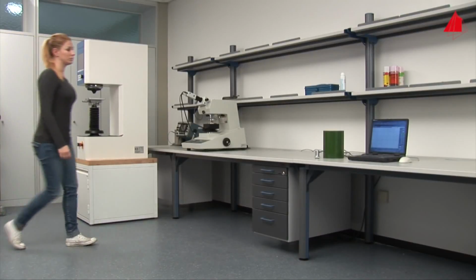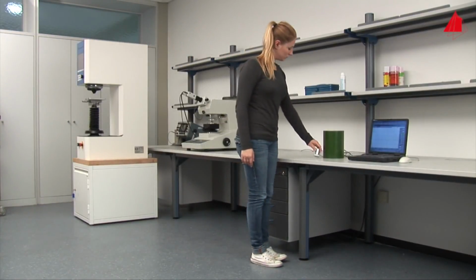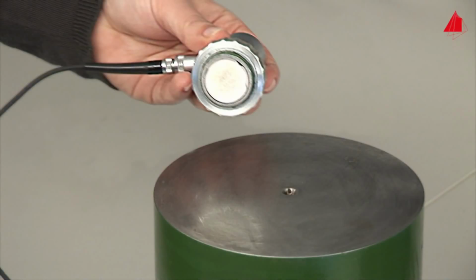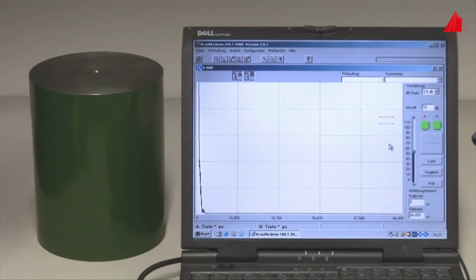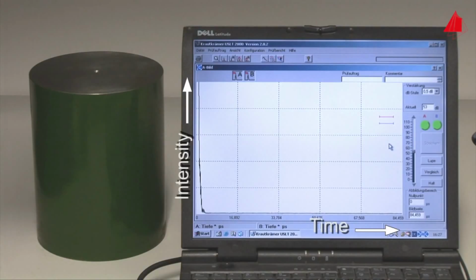To track down the defects, the material tester uses the pulse echo method. This is how a typical probe looks. Under the bright wear plate, a piezoelectric disc is installed. It can transmit and receive ultrasonic pulses. A computer operates the probe via a plug-in card and power electronics. On the monitor, the intensity is plotted upwards and the time is plotted to the right.